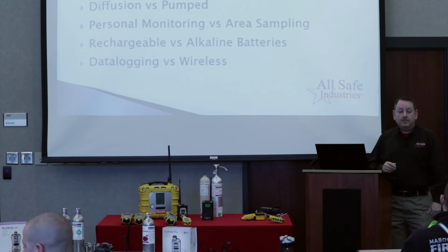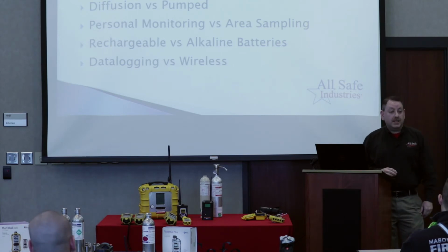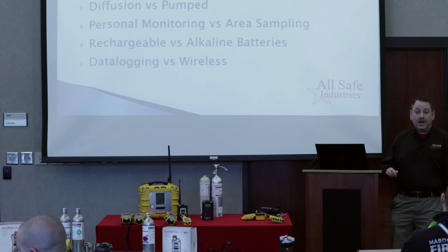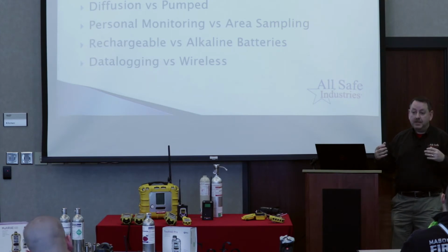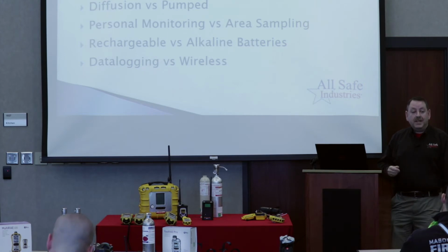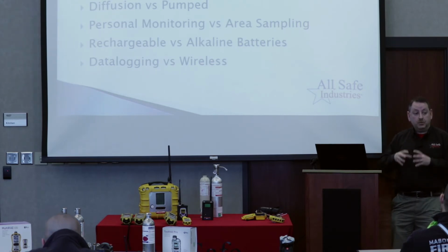And then the last thing I want to mention is data logging versus wireless. Like I said at the beginning, you guys did purchase the wireless option. So wireless means we're actually sending that data out from the instrument, and we can capture that information with a receiver so that we can get those readings on more than just the instrument. That's different than data logging. Think of data logging as a recorder. Data logging is where the instrument will record your readings, and then you can download those at a later date, versus wireless, which is real-time readings that we're sending to a receiver that's close by, okay?